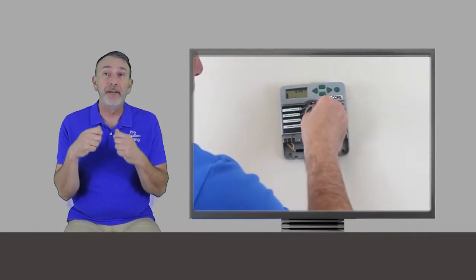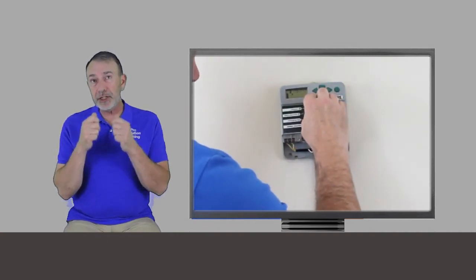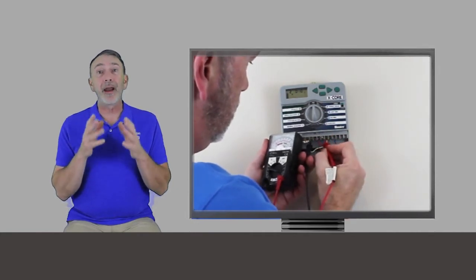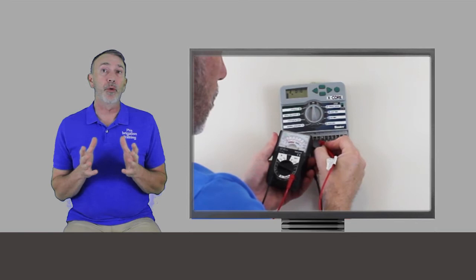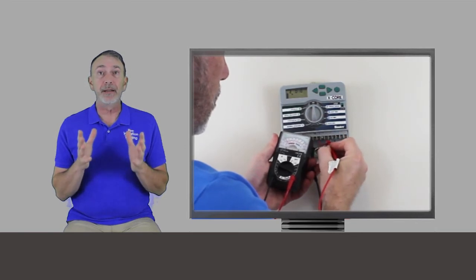To determine if it's the timer, mark the wiring diagram or take your phone out and snap a picture of the terminal strip to make sure you can put your wires back in the correct place. Turn your timer to the off position and remove all your wires. Now manually turn that zone on from the timer and recheck the voltage on that zone and then check your other terminals as well. If you're still getting voltage across more than one zone, you've got a bad timer. There's a short somewhere on the circuit board. Replace it.